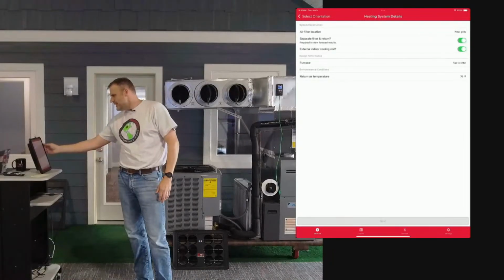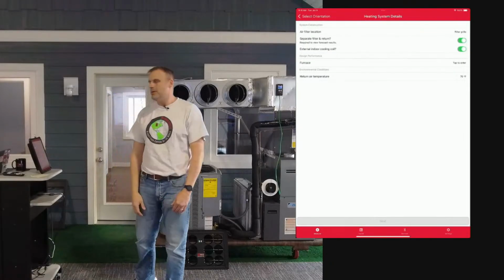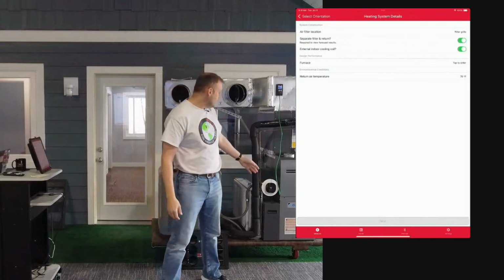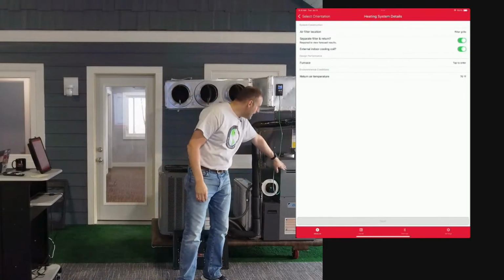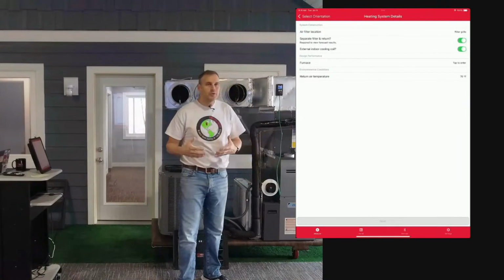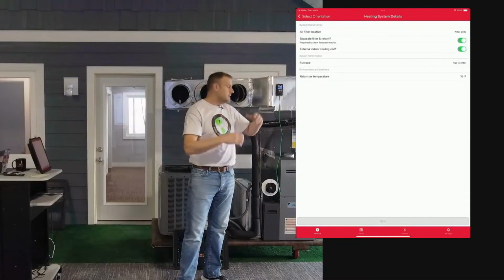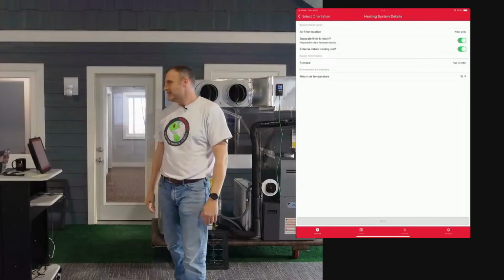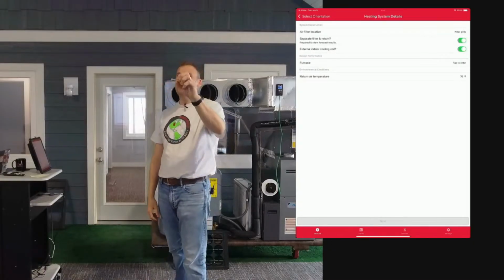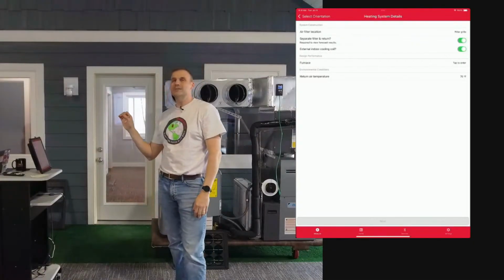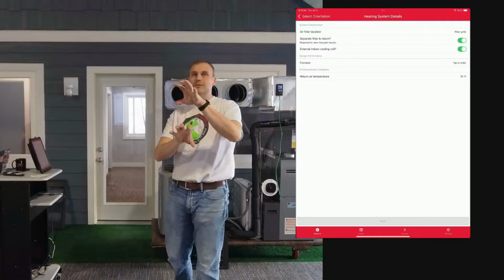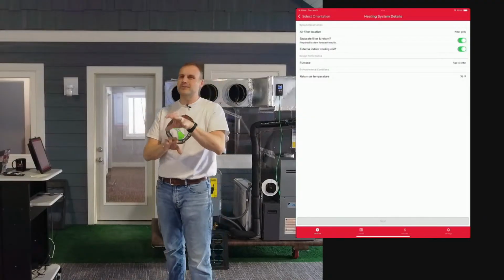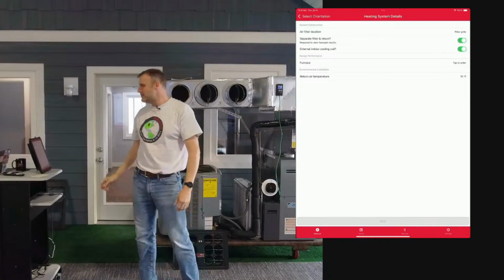Okay. External indoor cooling coil. What does that mean? That means that the system I'm testing has a coil that is after the furnace. The coil is external from the piece of equipment that has the blower in it. Now, I will tell you in a near future release, we plan to change that toggle to two images, furnace with a coil, furnace with no coil, to make that a little easier to understand. That's to come. That's on the improvement list.